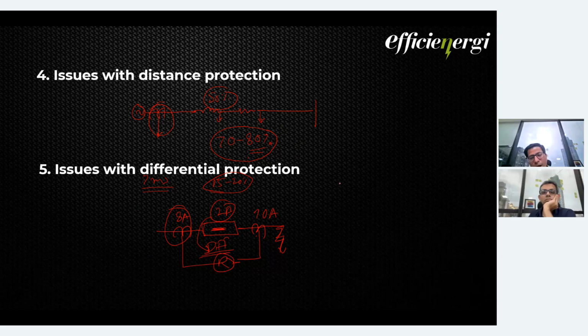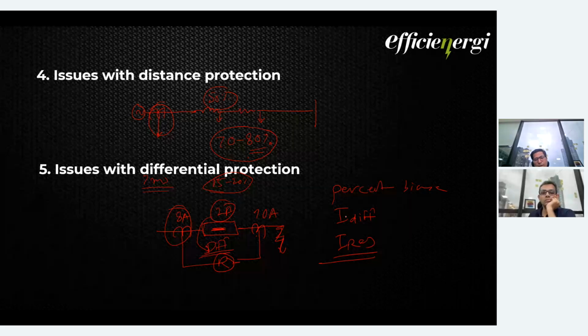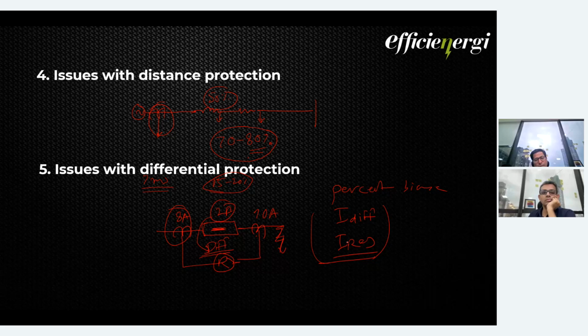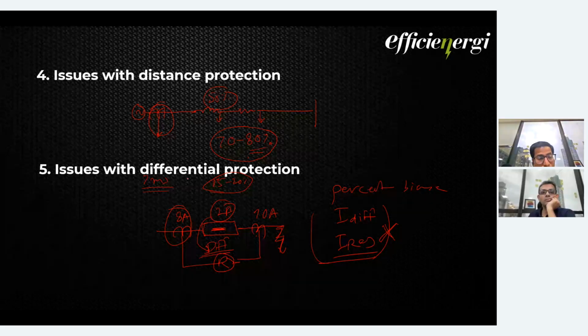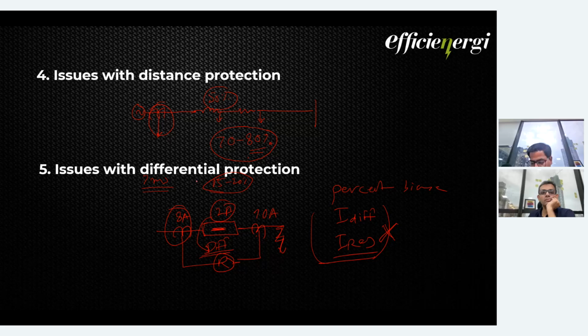Again, for differential protection we have a logic called the percentage bias scheme, wherein along with the I differential we have the I restraint current also. So to some extent we can avoid the saturation problem by using this philosophy or scheme. But again, if there is very heavy saturation, this will also not work. We will talk about this in more detail when we cover differential protection in upcoming webinars.